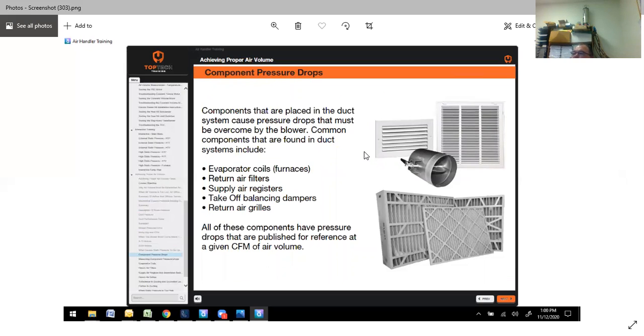Component pressure drops. It's important to know what's going on. Components that are in the duct systems include evaporator coils, if they get dirty; return air filters, if they're too restrictive; supply air registers, if a bunch of them are shut off or there are not enough; takeoff or balancing dampers, if they're not opened; and return air grills.